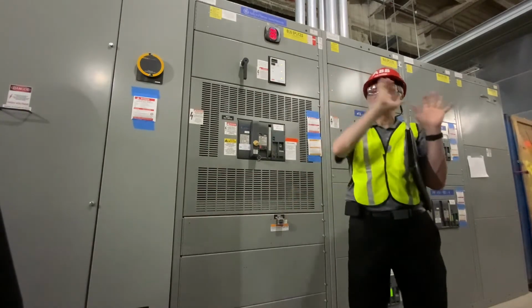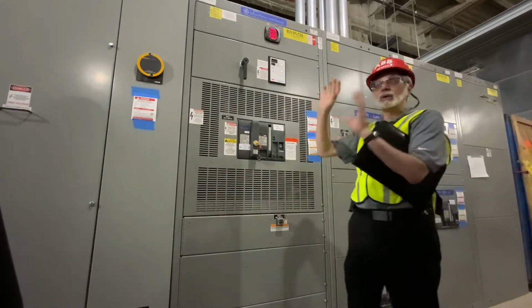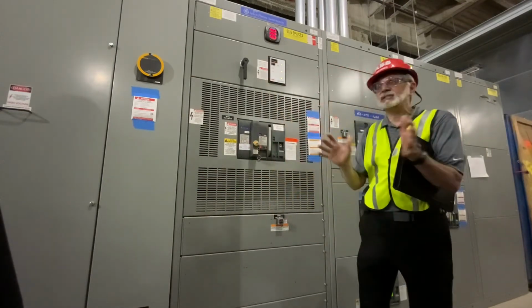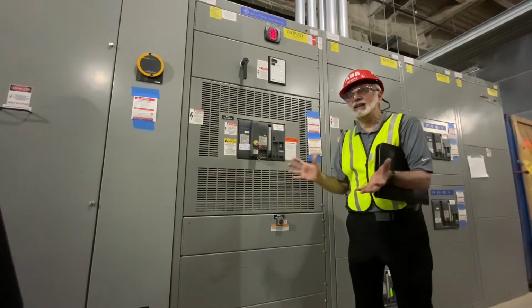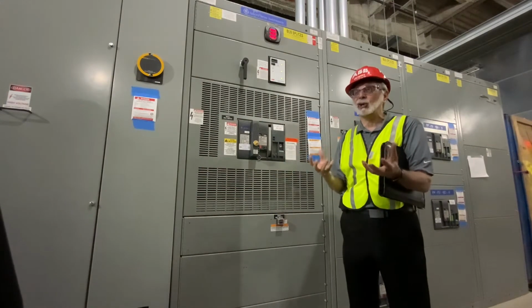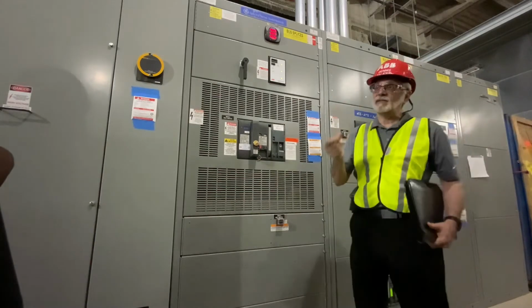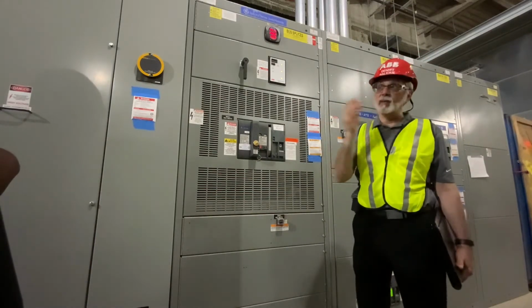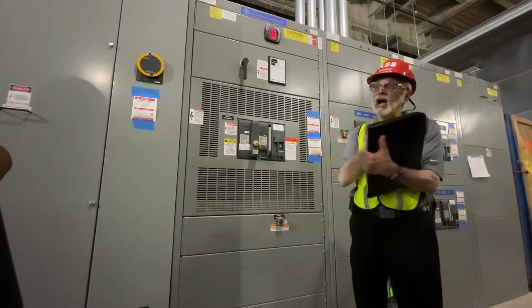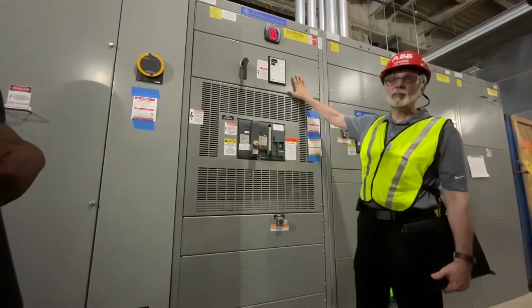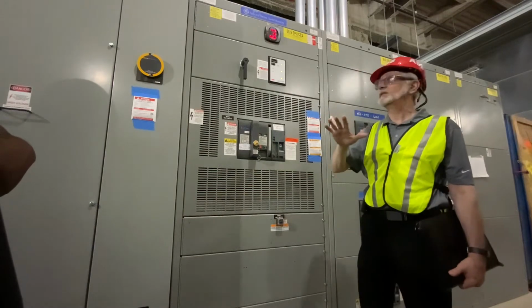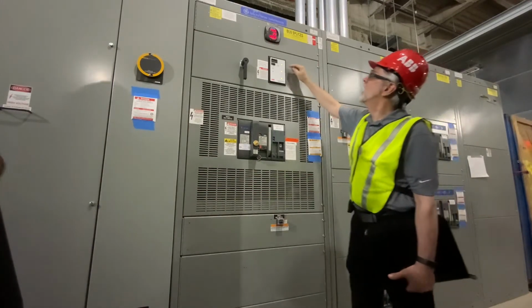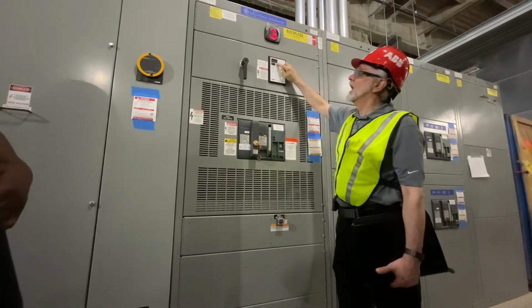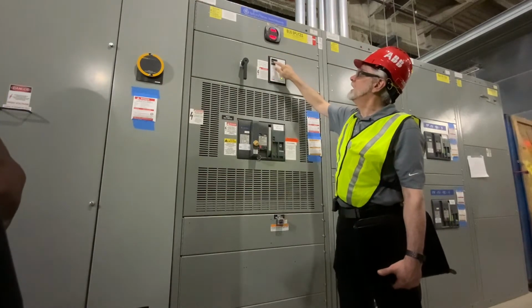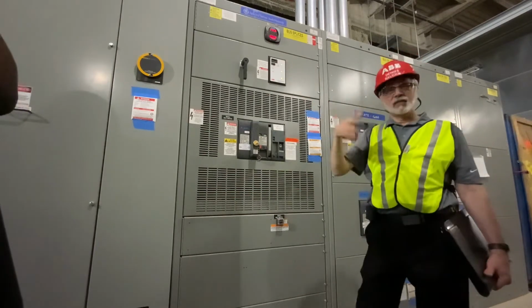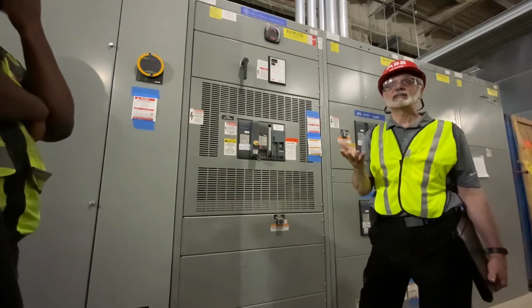Everybody thinks it's switching surges from the utility, or a lightning strike from the storm. Yes, that's true, but 75 to 90% of them are usually generated internally. And so the nice thing about this is, if you're getting those switching transients from your large chiller devices because of the contactors slapping in and out, this will help dampen that out. If you do have any severe transients, not only will it capture them, but you also have a counter on here. So if you ever come up here and see numbers on it, then you'll know that you have experienced some transients.